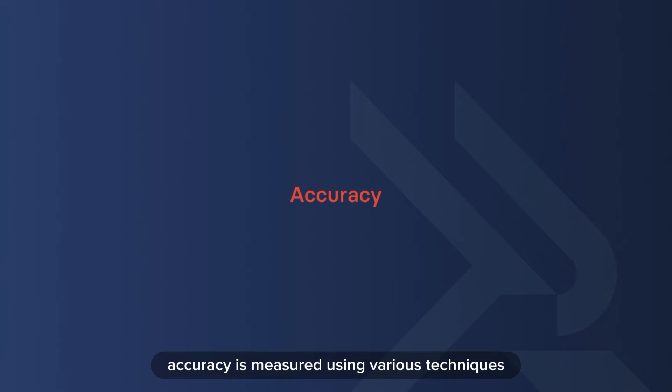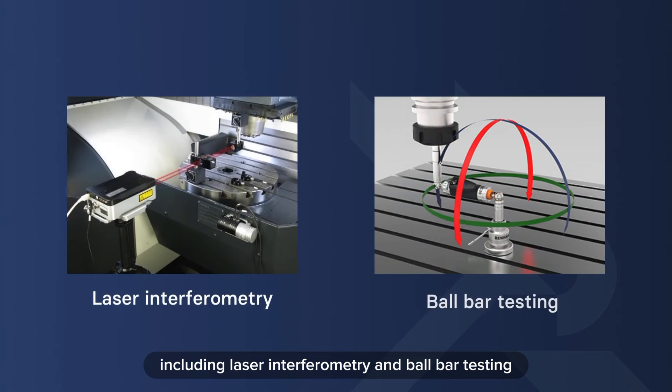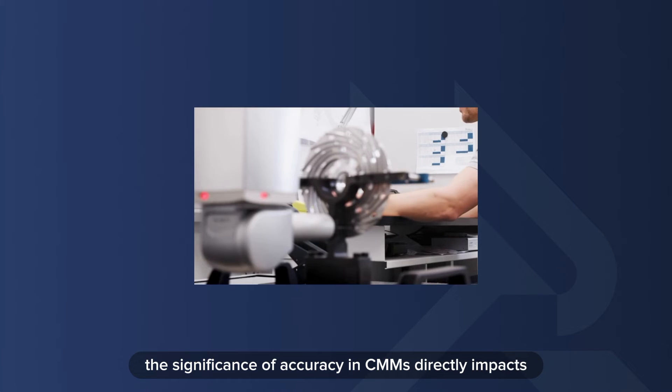Accuracy is measured using various techniques, including laser interferometry and ball bar testing. These methods help calibrate the CMM and ensure it performs within specified tolerances.